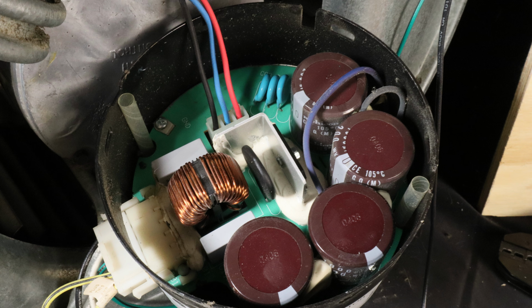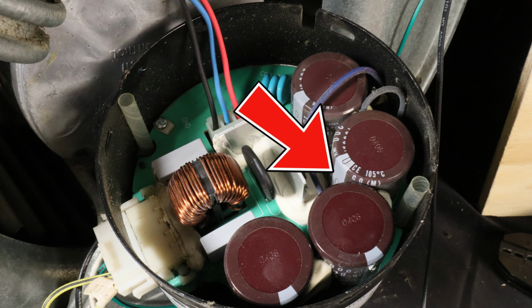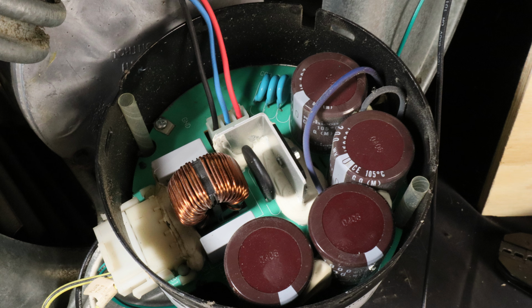But you want to make sure that these capacitors you see over here on the side bleed out. They do have bleed out resistors, so they will discharge, but you have to leave it unplugged and unpowered for at least, I would say, 15 minutes before you ohm out that thermistor. Now, what you should read will vary on different types of motors. Sometimes you might see 4 to 12 ohms. Sometimes you might see them as low as 1 to 3 ohms. But basically what you're not looking for is either OL, that means the thermistor is bad, or you're reading very low or no resistance at all.